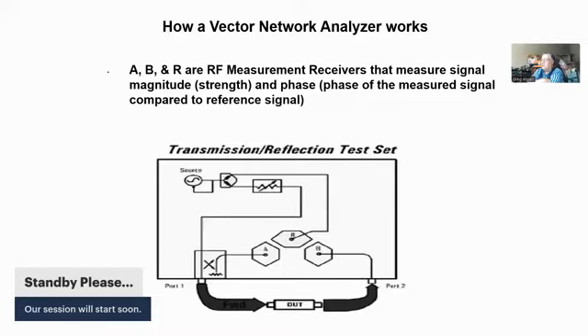comes out of port 1 and goes into the device under test. That thing at the junction of port 1 there is what's called a coupler, directional coupler. And then any signal that's reflected back from the device under test back into port 1 gets coupled through that coupler and goes to receiver A. If you're dealing with a 2-port network and the signal goes through the device under test into port 2, the signal coming out of the device under test goes to receiver B.